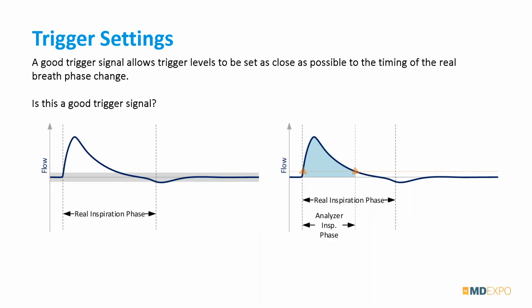If we just used the same threshold as for our start trigger on a falling edge, you would see a huge mismatch between our real inspiratory phase and the one that the test equipment actually measures. This is just an example to show you that if you have these trigger settings inappropriately set, it can make a big difference in measurements like rate, inspiratory time, or peak pressure.